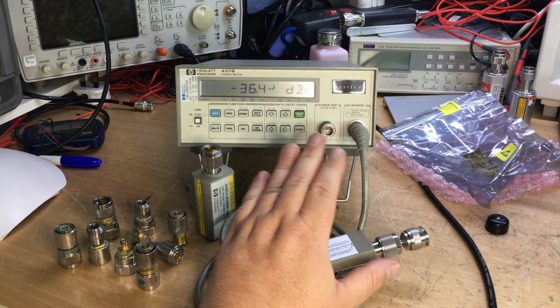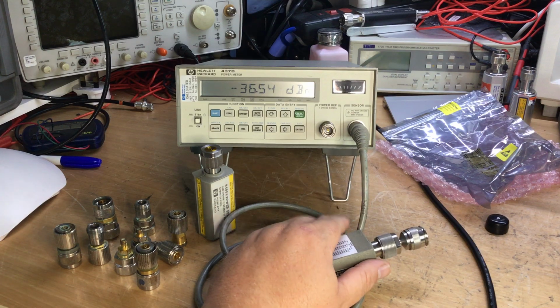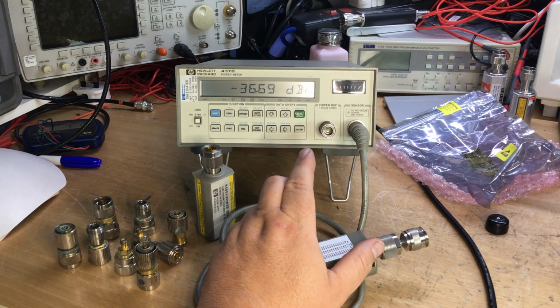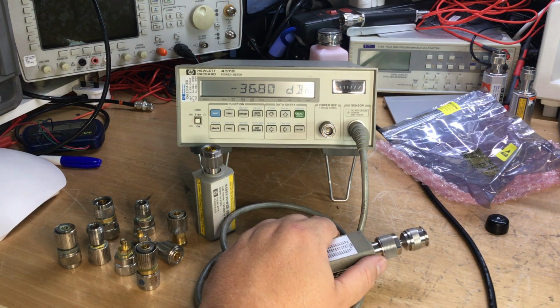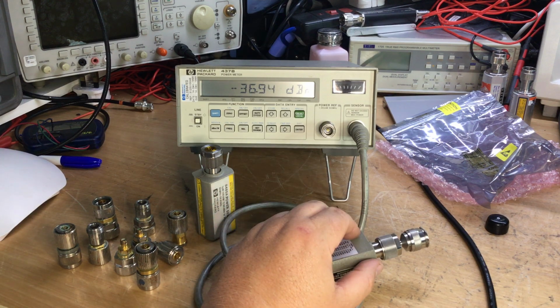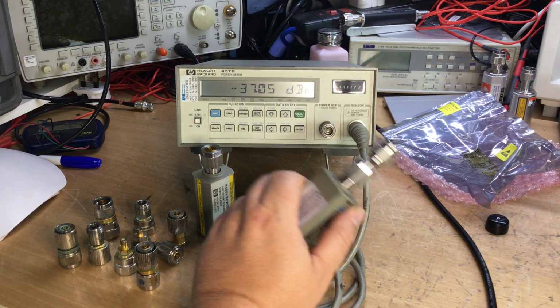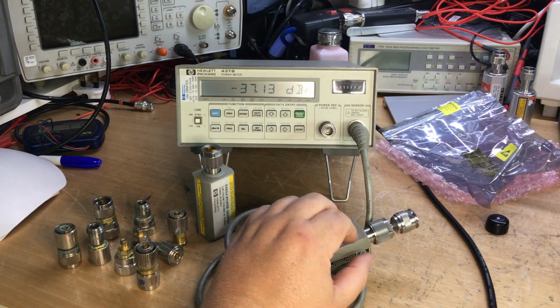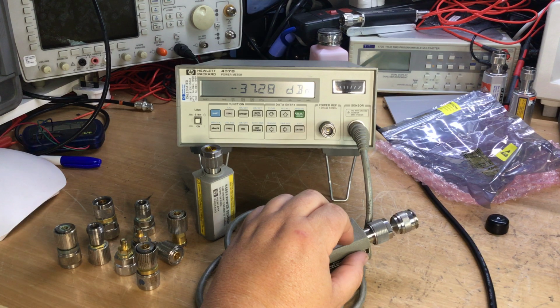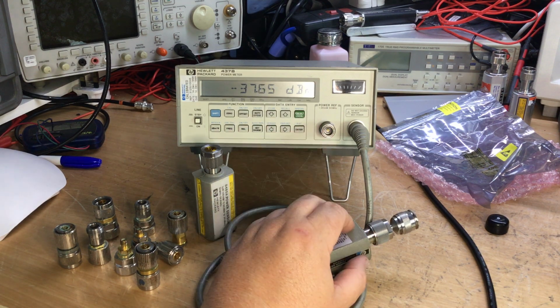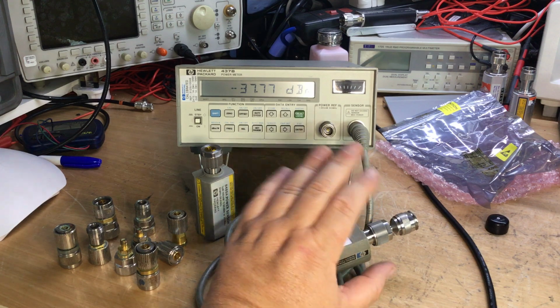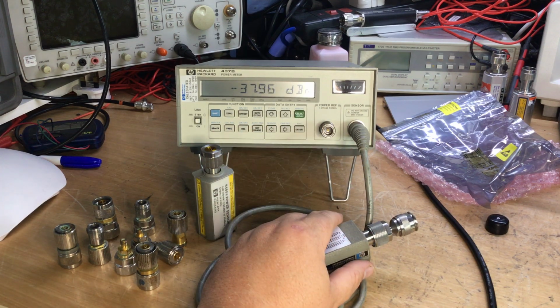So obviously that's the first thing we'll do after we've entered all the cal data in, set the meter up correctly so that the sensor will calibrate properly. Then, using the Marconi microwave radio test set, we'll check the 50 meg reference coming out of this meter for accuracy as well, and we'll also do some sweep power measurements using this particular sensor across its entire frequency range to 26.5 gigahertz. So let's have a look at the Marconi equipment that we're going to use to test both the meter and this sensor as well for accuracy.